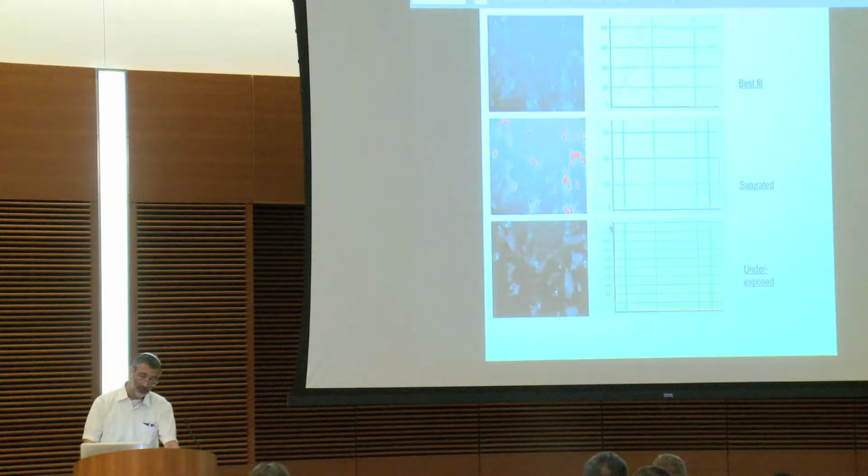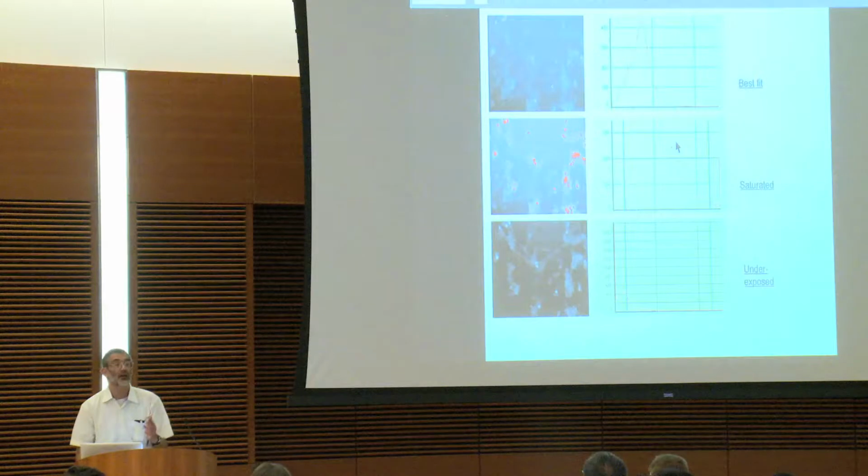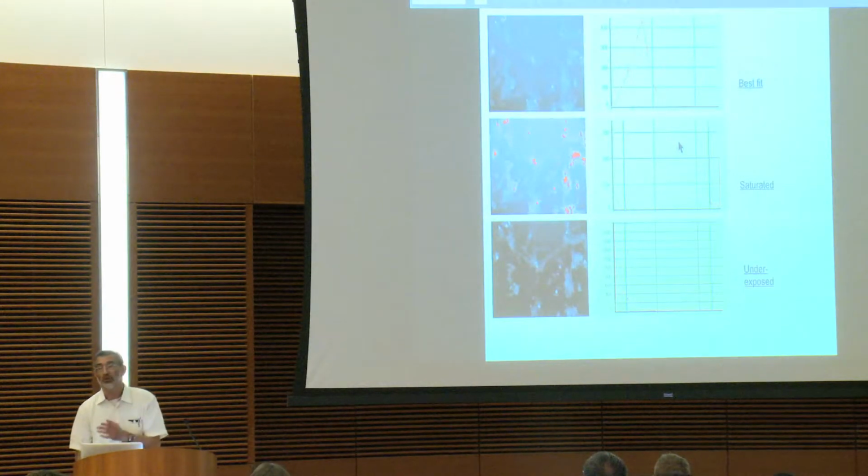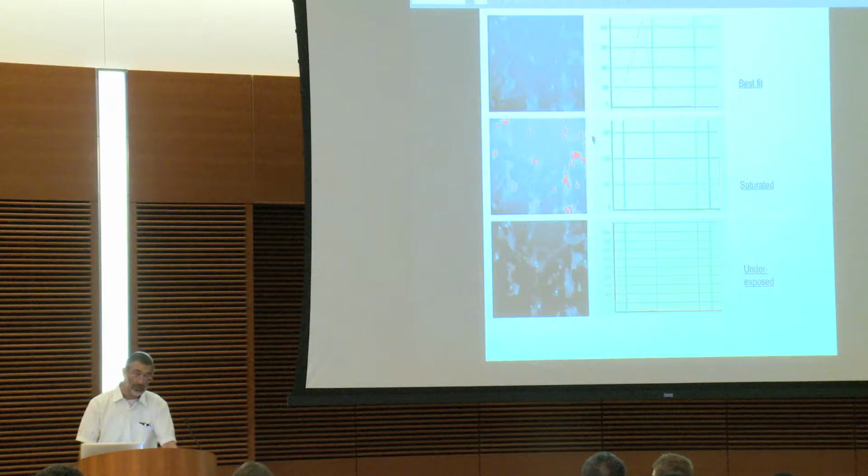And if you got a big peak at the 0 here, that means your image is too dark. Most of your pixels should sit in the middle. That's why lookup tables on many image acquisition devices, confocal microscopes and so on, have this high-low lookup table where values below 5 are, let's say, green, and values above 250 are red, or something like that. And then in the middle, it'll show the grayscale.